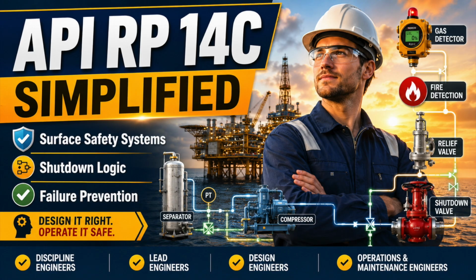Overpressure protection demands particular discipline. A high-pressure shutdown attempts to stop the pressure source before the equipment limit is reached. A relief device protects against failure, delay, or unremoved pressure generation. Do not assume that fast valve closure automatically replaces mechanical relief.